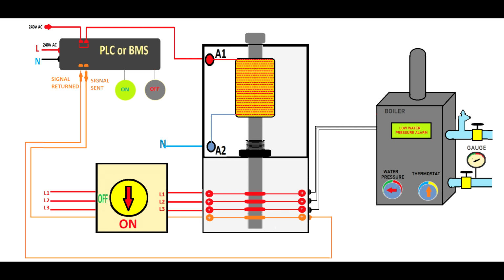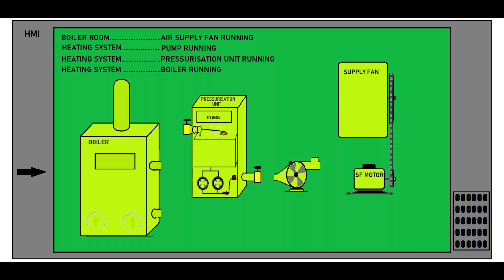Although when the client calls the people who remotely monitor the heating cooling system, they will send the wrong engineer. Like if the boiler is not running, you might send a gas engineer, but the boiler might not run because of the pump or the fan, and then you need a trained HVAC engineer, or you might need a trained electrician. So if you look at this picture now, the HMI will tell you that everything is okay, which might not be true. This HMI will only tell you the status of a contactor and of an isolating switch. However, you can see it will display on the computer all these items which are supposed to work as working, but which is not always true.